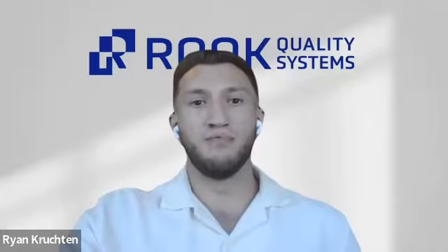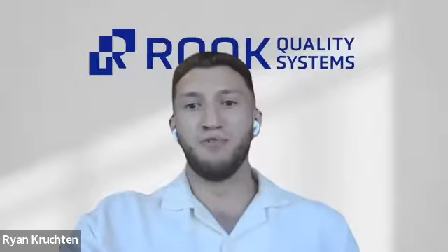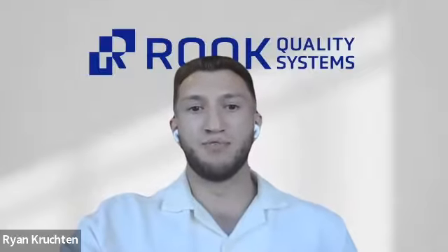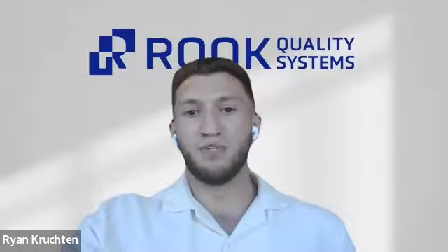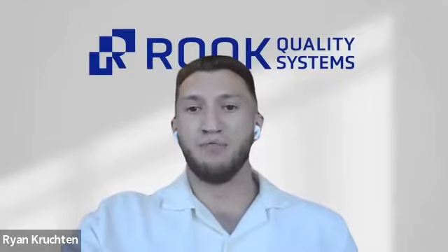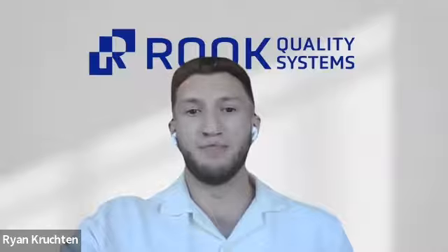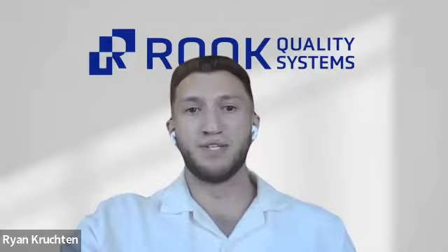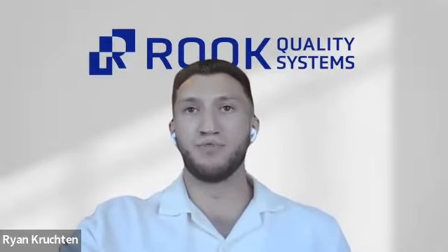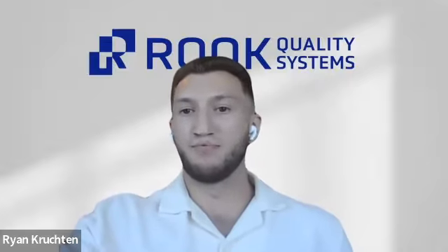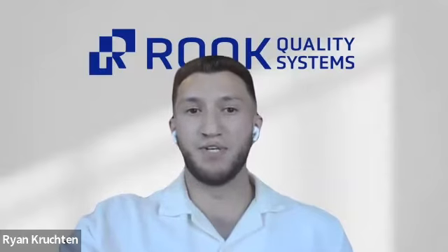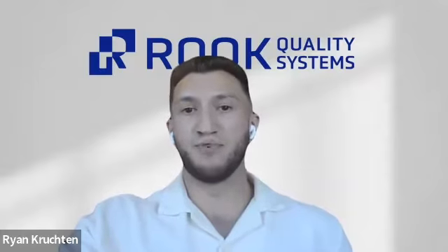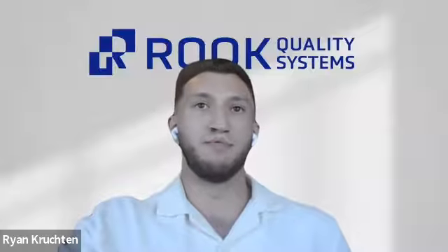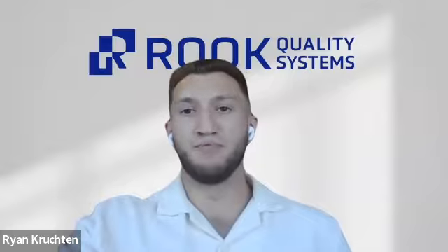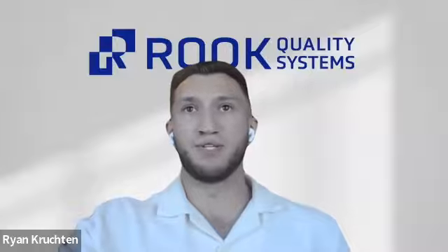All right, so for software development approaches and tools, your methodology matters just as much as your coding tools. Whether you're using tools like Jira or Git, the key is how they support traceability and collaboration along with compliance. Traceability is a critical concept for understanding how all of our user stories or user needs, software requirements, detailed design specifications, test cases, and test reports all come together to tell the story of compliant development. And that was beautifully illustrated in Veronika's last slide.